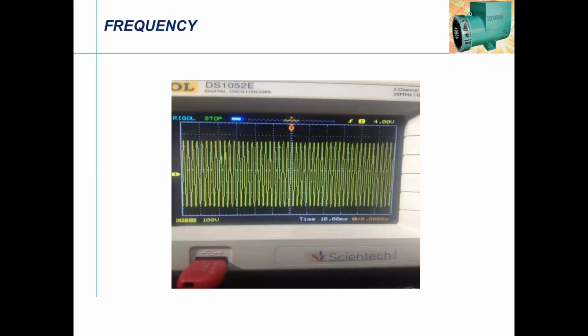And this is your current. Always the current follows the voltage, we call that lag. If the voltage follows the current, then it becomes leading. So the generator should be operating on unity or lag. It can also operate in some conditions in the leading, but that is not good for it, which I will share on the particular information. This is again an important frequency.